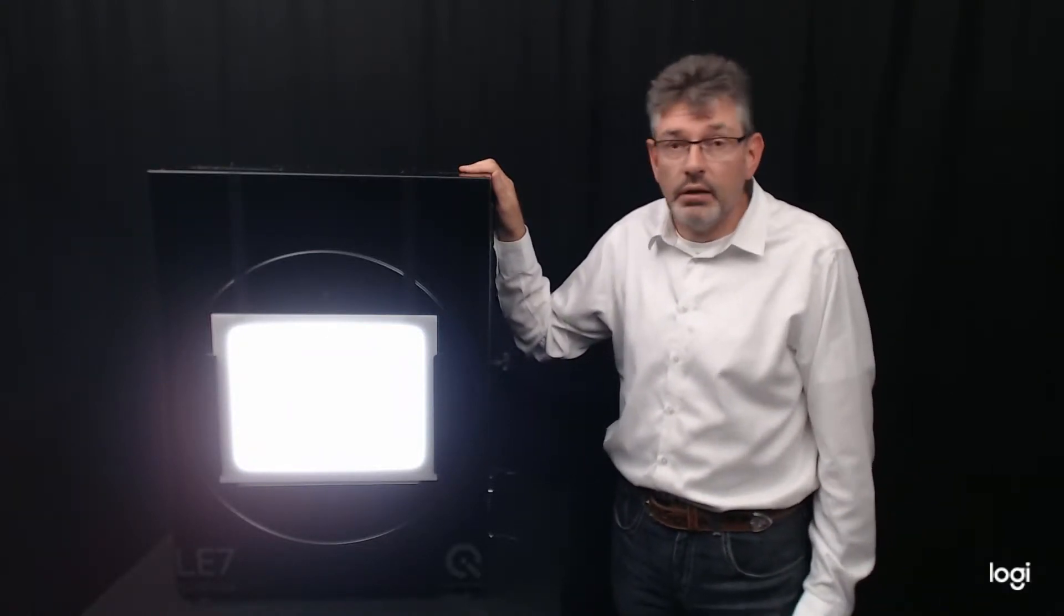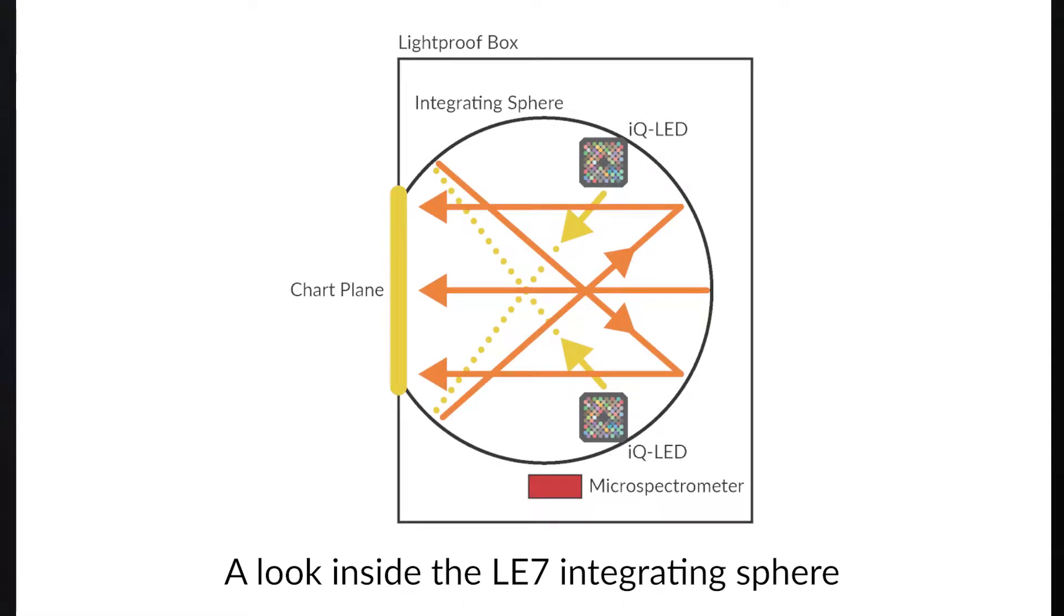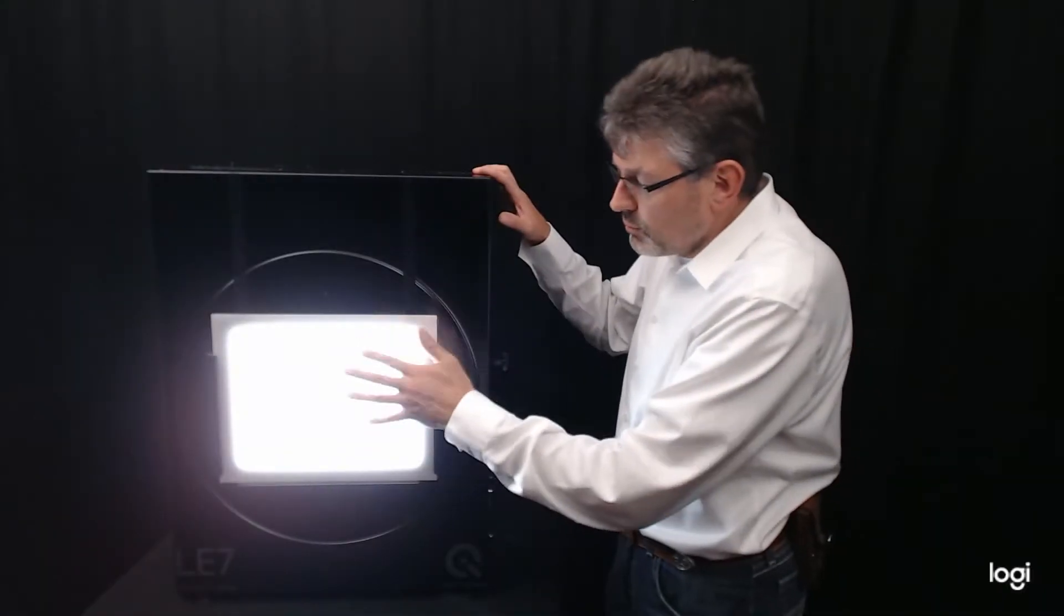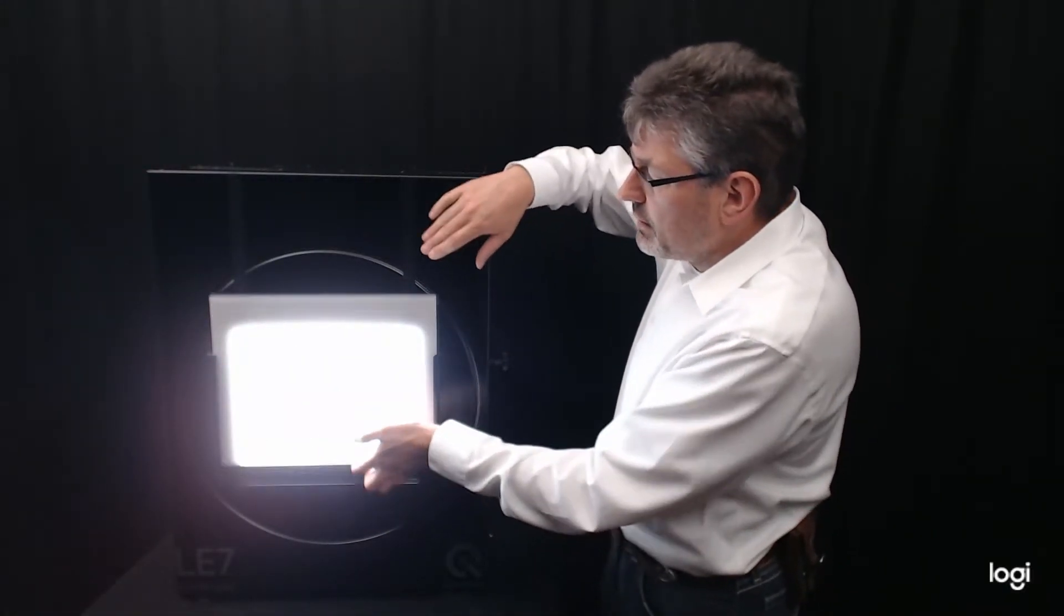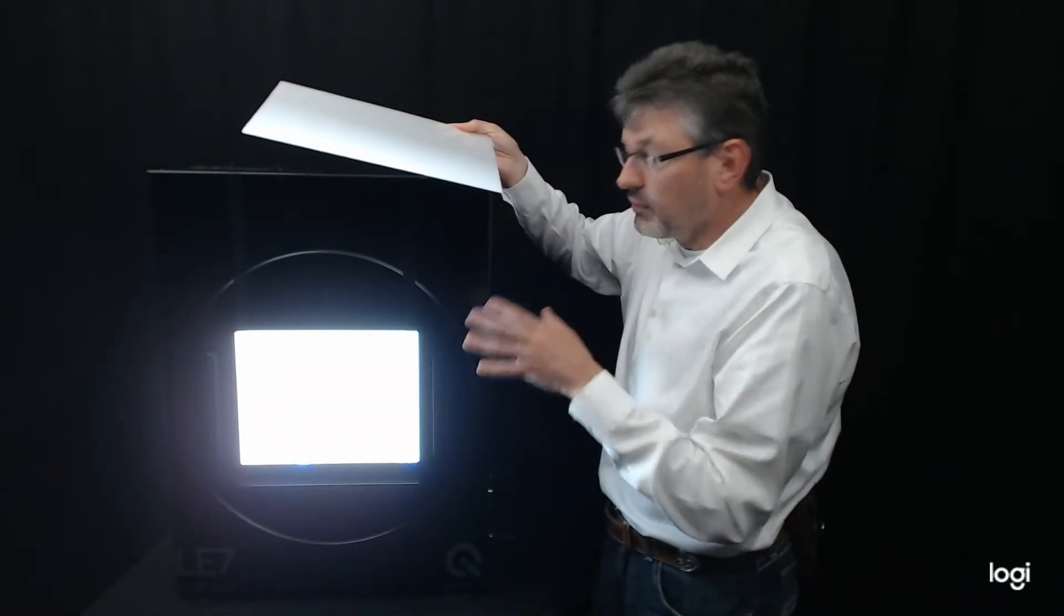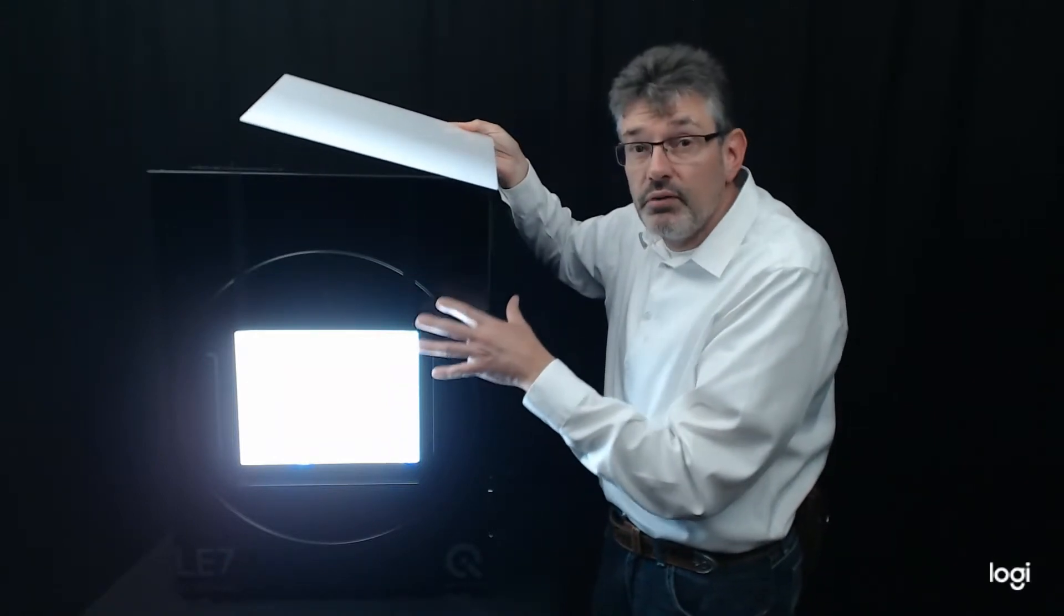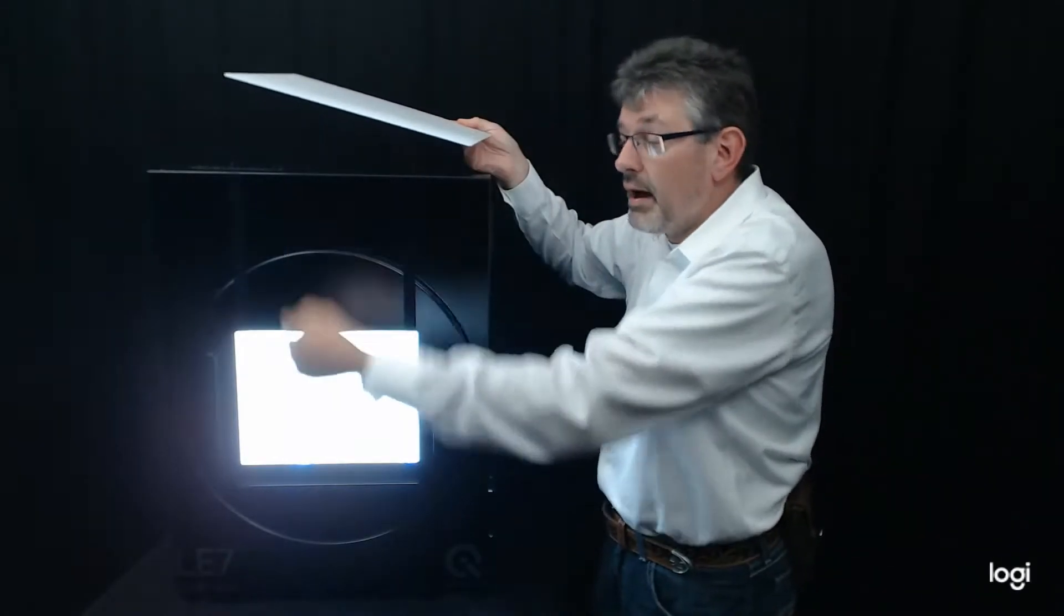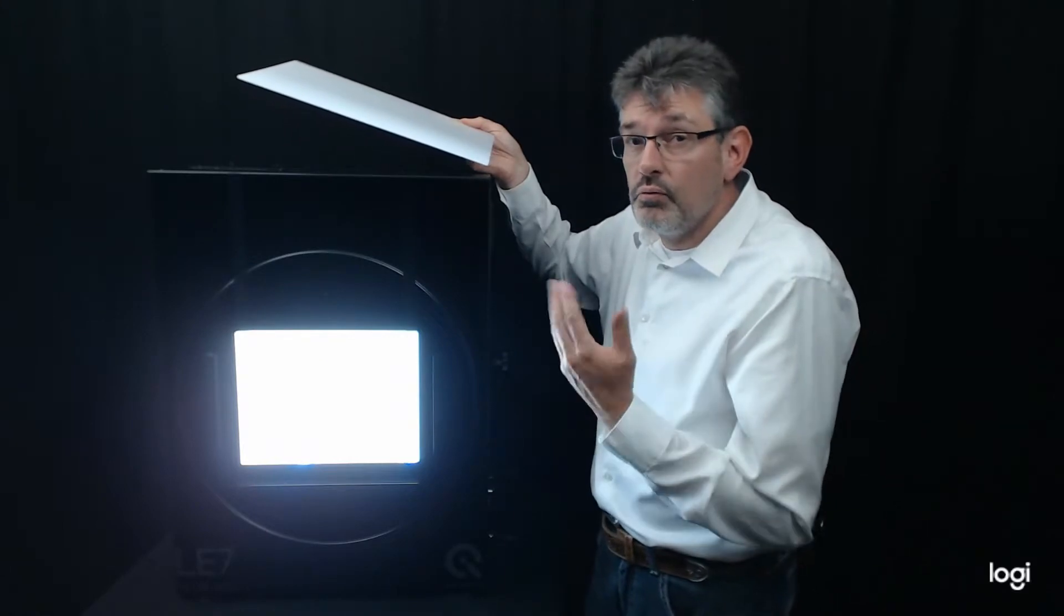So what is an integrating sphere? An integrating sphere is basically a sphere that is coated white on the inside and you shine light into it, and perpendicular to that direction you have a light outlet that is then uniformly illuminated. So as you can see here we have the outlet of our integrating sphere. Inside here we have a sphere. Yes, the whole thing doesn't look like it, but there is a sphere inside. We just need that housing to make it light proof for the various applications.